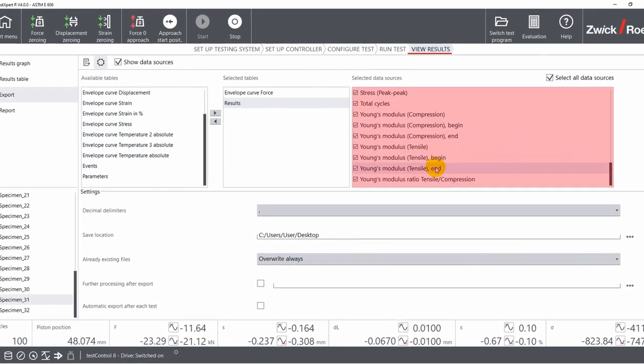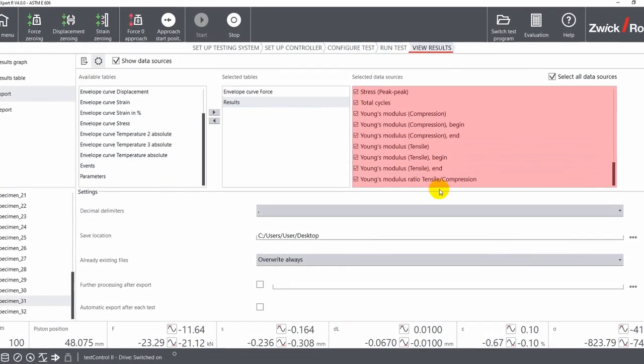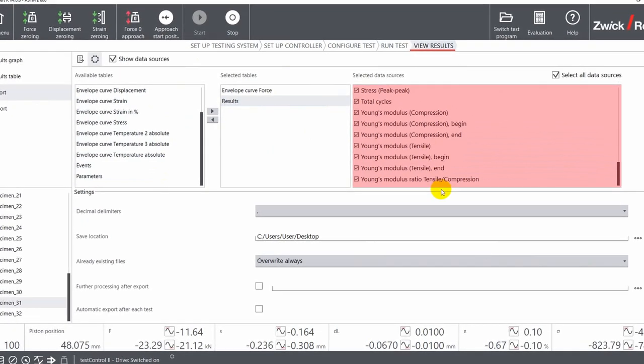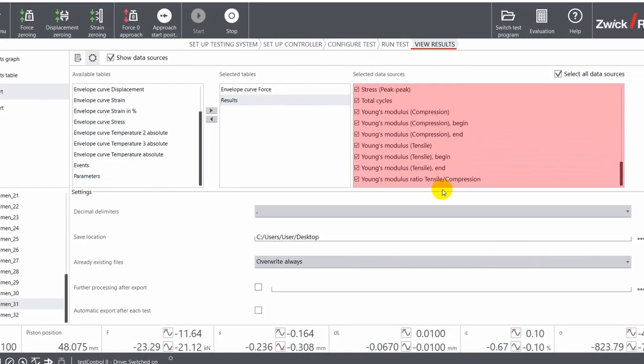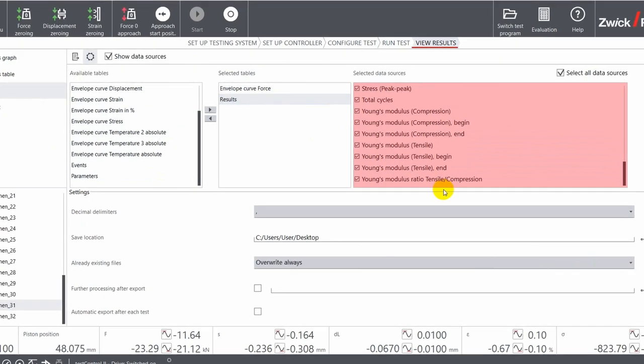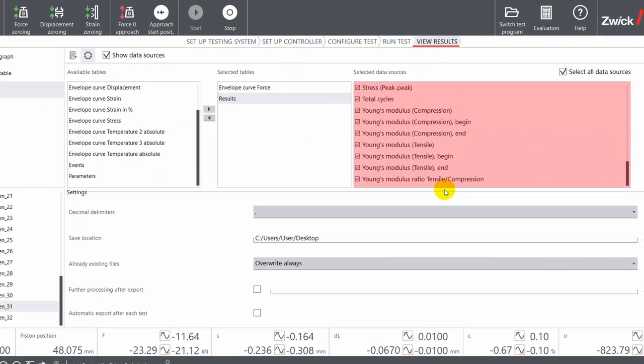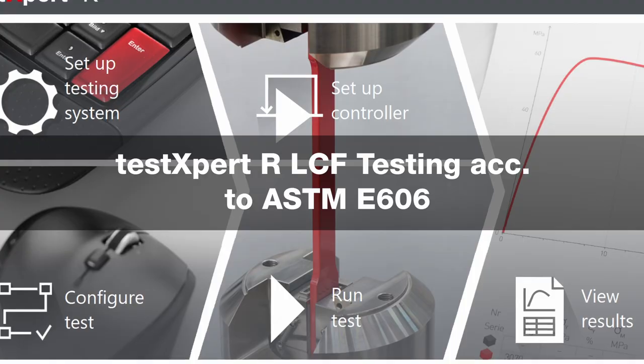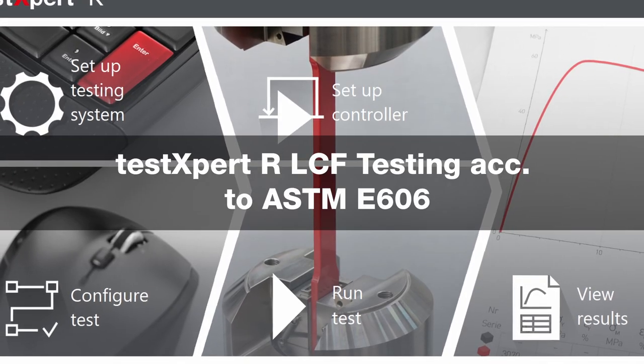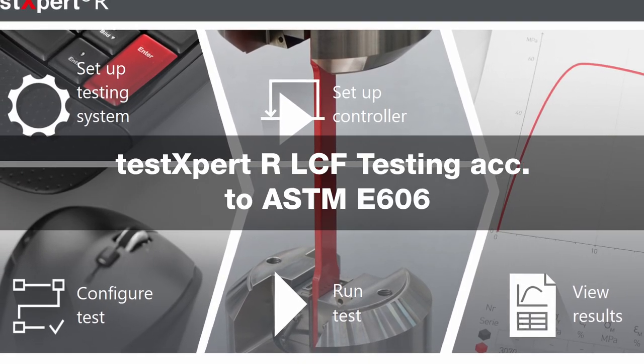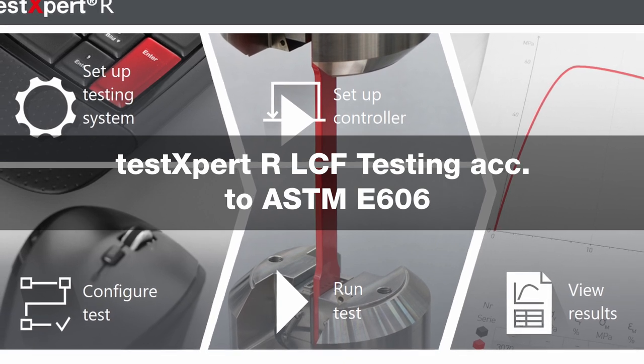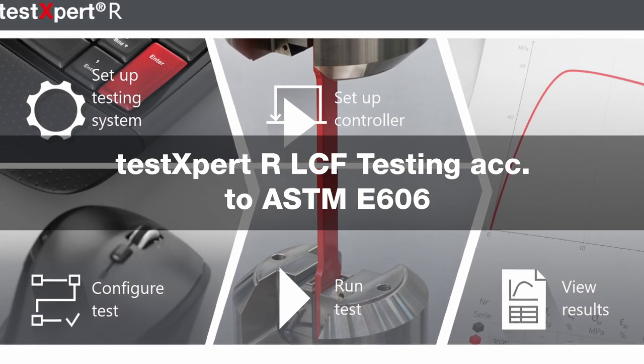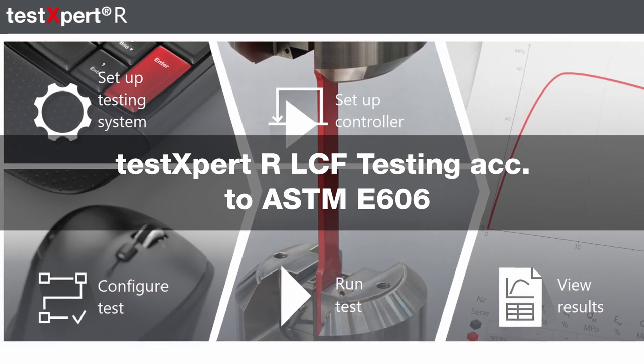Compared to a standard fatigue testing program, this software allows you to export LCF-specific results such as plastic and elastic strain and the Young's modulus in tensile and compression direction for each recorded hysteresis. As you can see, the test program for LCF testing is simple and intuitive and guarantees reliable test results according to the ASTM E606 standard.